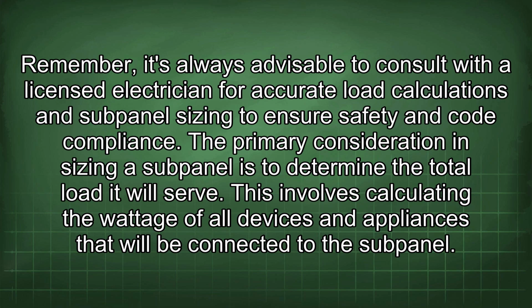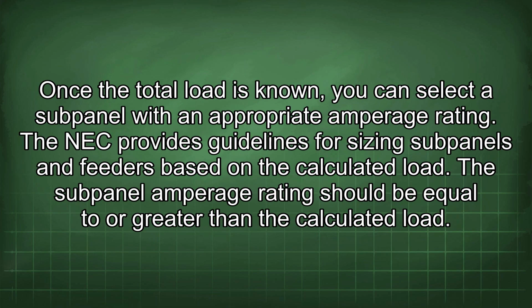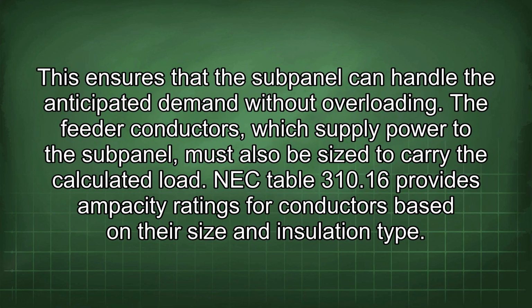This involves calculating the wattage of all devices and appliances that will be connected to the subpanel. Once the total load is known, you can select a subpanel with an appropriate amperage rating. The NEC provides guidelines for sizing subpanels and feeders based on the calculated load. The subpanel amperage rating should be equal to or greater than the calculated load. This ensures that the subpanel can handle the anticipated demand without overloading. The feeder conductors, which supply power to the subpanel, must also be sized to carry the calculated load.